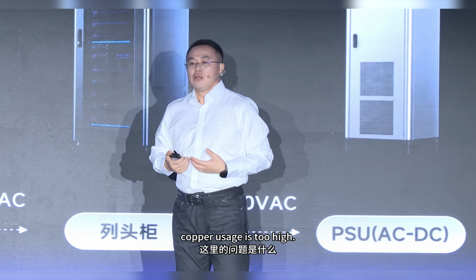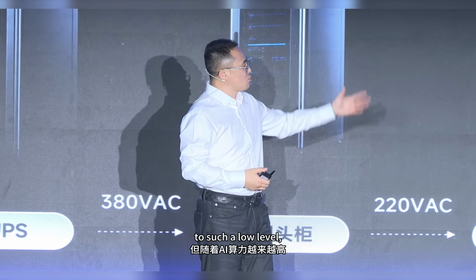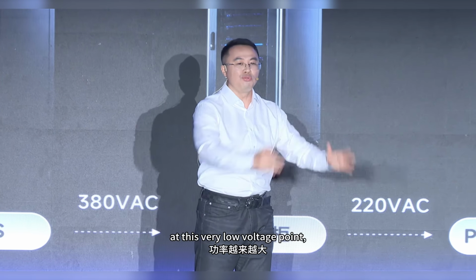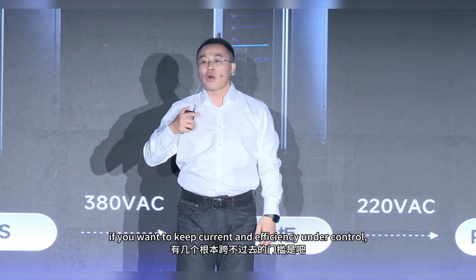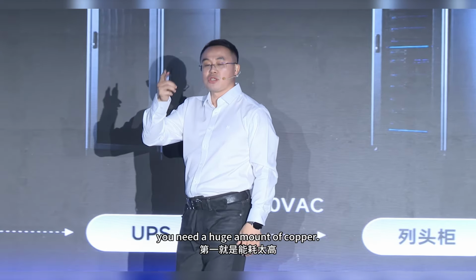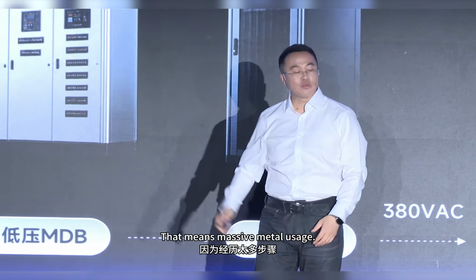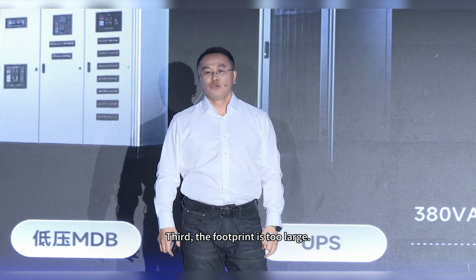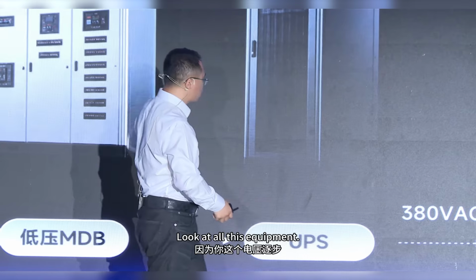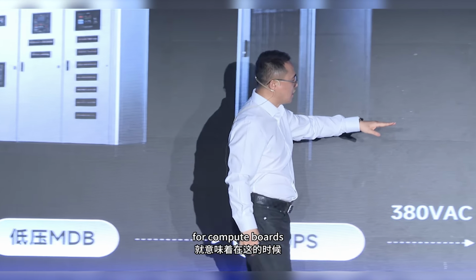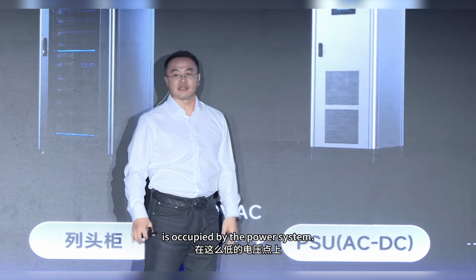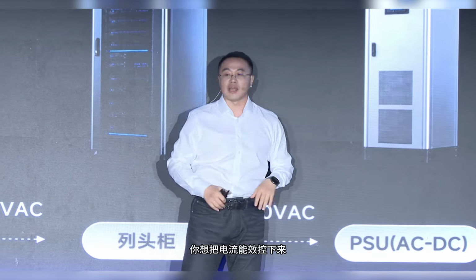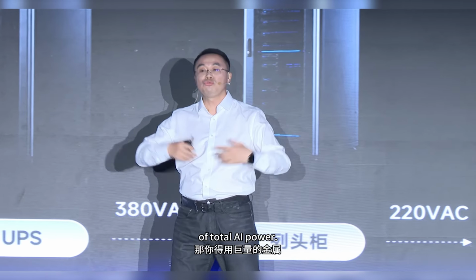Second, copper usage is too high, as voltage keeps dropping to such a low level. If you want to keep current and efficiency under control, you need a huge amount of copper, meaning massive metal usage. Third, the footprint is too large. Look at all this equipment; space that should have been used for compute boards is occupied by the power system. These three big problems constrain the rise of total AI power.